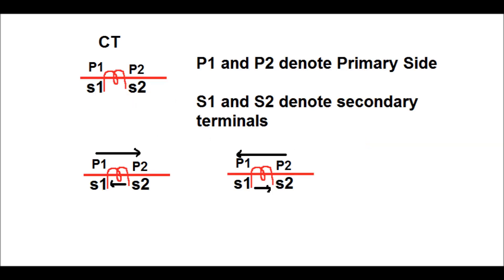The symbol of the current transformer is shown in the picture above. P1 and P2 are the two terminals for the primary side of the CT, and S1 and S2 are the secondary terminals. When current flows from P1 to P2 in the primary side, due to transformer action, the current will flow from S2 to S1 in the secondary side. Similarly, when current flows from P2 to P1 in the primary side, the secondary current flows from S1 to S2.